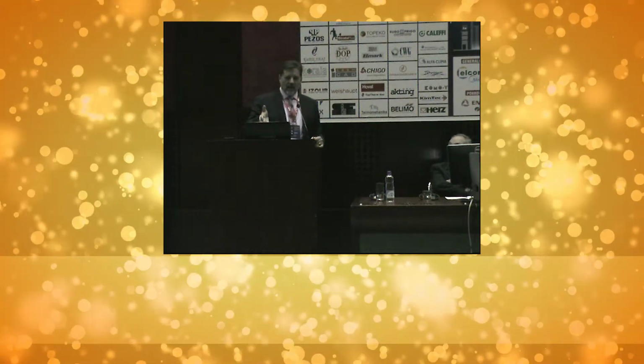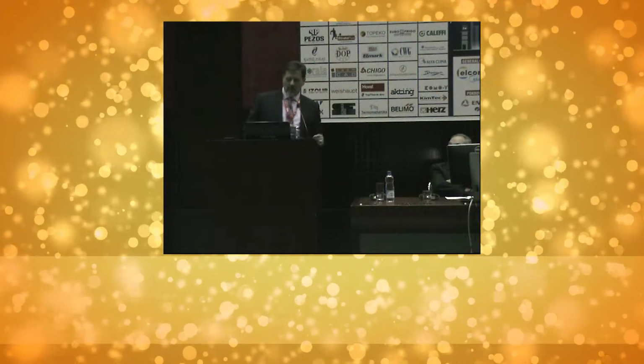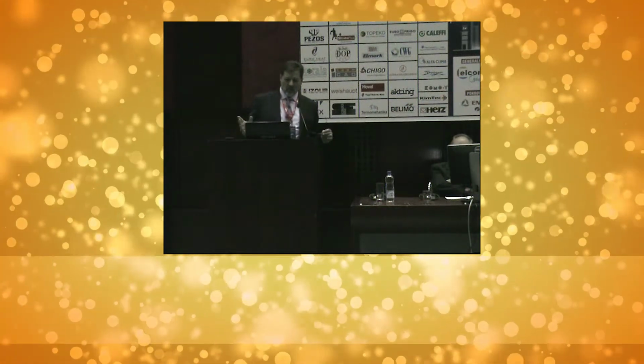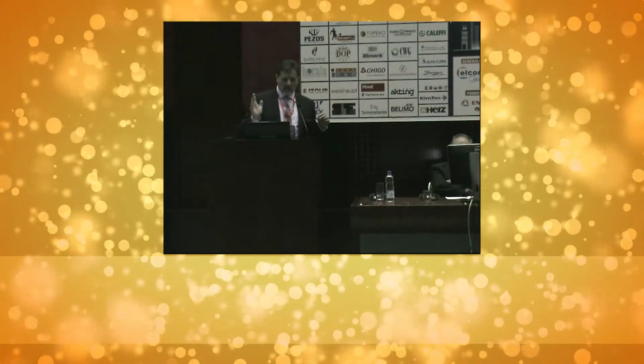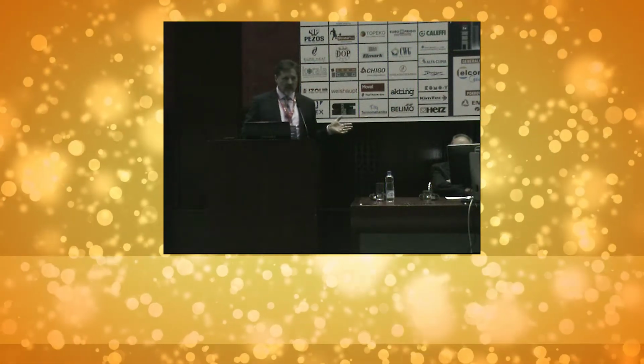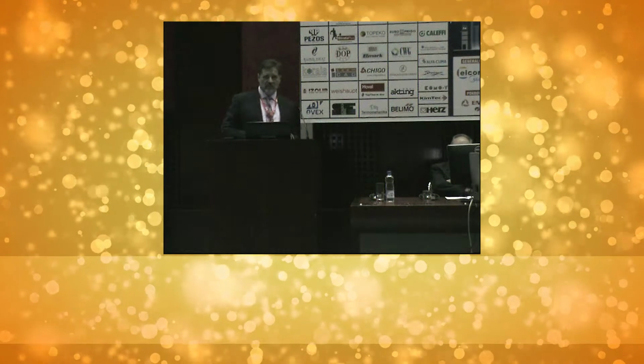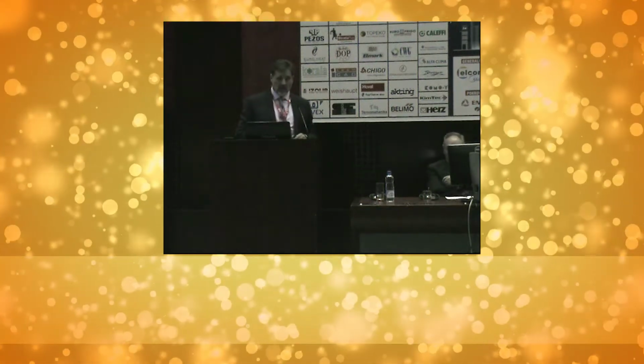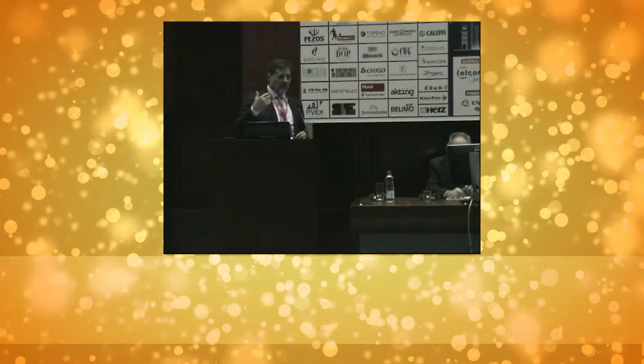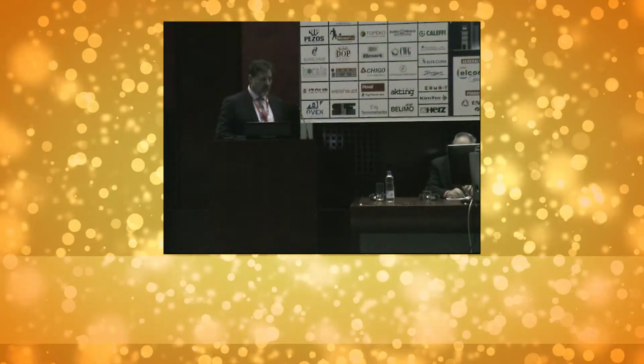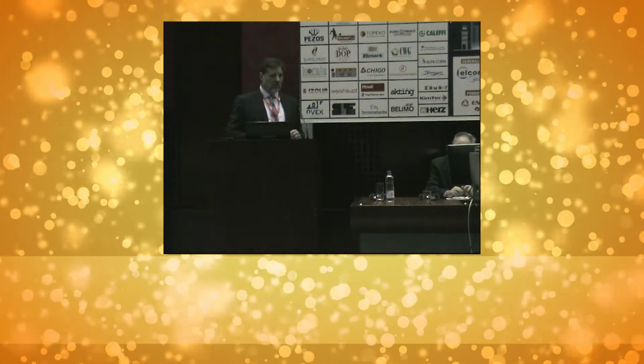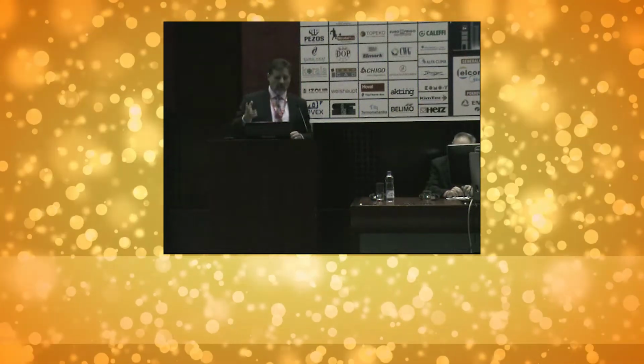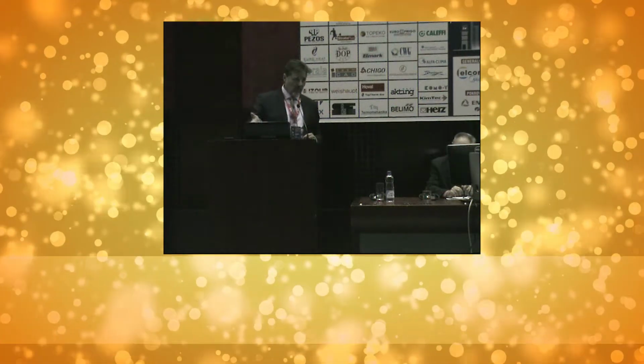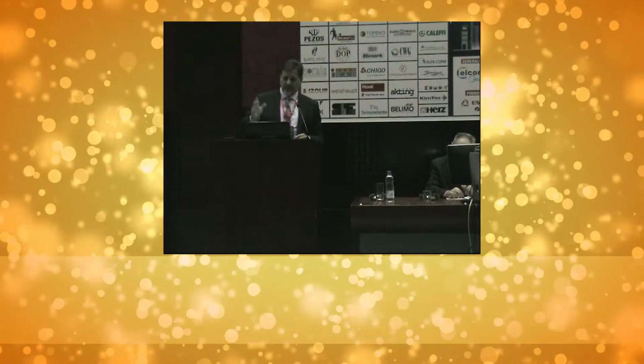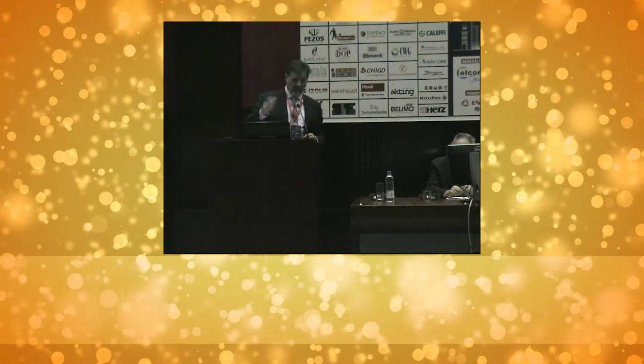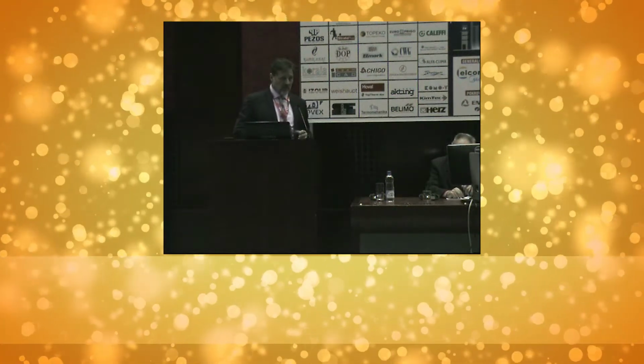So, I tried to squeeze all this research of 2 years into one talk. Just pay attention: change your sensors from the classic delta pressure sensors to the thermal dispersion. It will pay back very quickly. You're going to be a lot more advanced. You can follow the ASHRAE 62.1 requirements very closely. You can reduce the consumption of energy. You can reduce everything. And the CO2 mode is going to be very simply regulated. Anything that you can do with the thermal dispersion, just go for it.